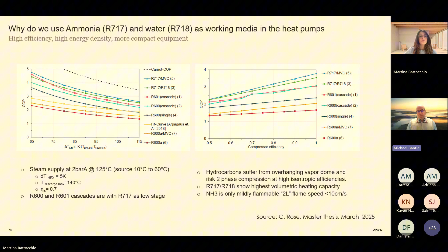If we compare COPs over certain temperature lifts for this system combination with other combinations, hydrocarbons or other working media, we see that it comes out on top in most cases, meaning it's the most efficient combination for the temperature lift that we are covering with our heat pump, a temperature lift from, let's say, 30 degrees up to 120, 130 degrees.